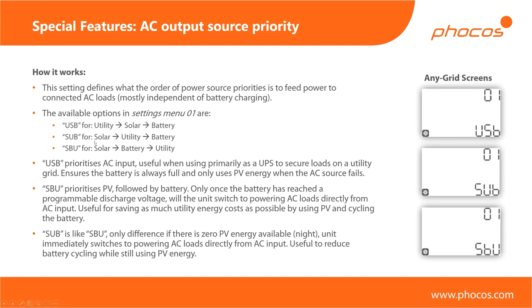The second option is Solar-Utility-Battery (SUB), which prioritizes PV as the first priority. Whatever energy you're producing from your solar panels, you use that directly for your loads and charge your battery at the same time. Utility is the second priority, but there's no hard switchover between grid and off-grid. For example, if you're producing one kilowatt from PV and need two kilowatts for your loads, one kilowatt comes from solar and the remaining kilowatt is mixed in from the grid simultaneously — no hard switching.